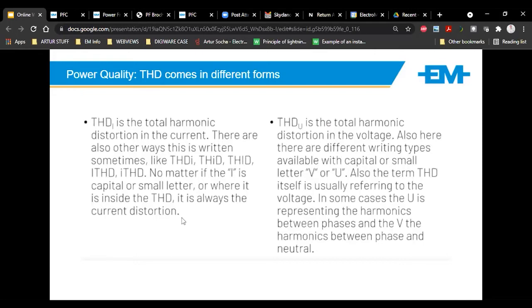Now, a voltage harmonic is inherently created by a current harmonic, by your load, because the utility says, I'll give you good power. Your current harmonic, if it's bad, and depending on the different orders, returns back to your transformer. Your transformer sees that and returns it back into your internal grid as a voltage harmonic. So it's a continuous little circle.